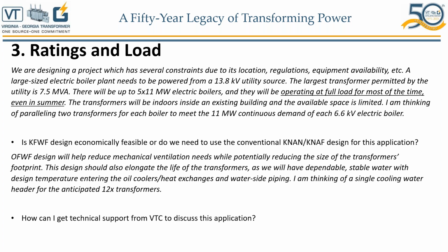And it says here they'll be operating at full load for most of the time, even in summer. The transformer will be indoors, inside an existing building, and the available space is limited. I'm thinking of paralleling 2 transformers for each boiler to meet the 11 megawatt continuous demand of each 6.6 kV electric boiler. Yeah, but if your maximum size of the transformer is 7.5 and you parallel 2, I don't know if you'll be able to get up to 55 megawatt, but that's your decision. I'm a transformer guy, not really the whole substation understanding here. What I will do, though, I will answer your questions.